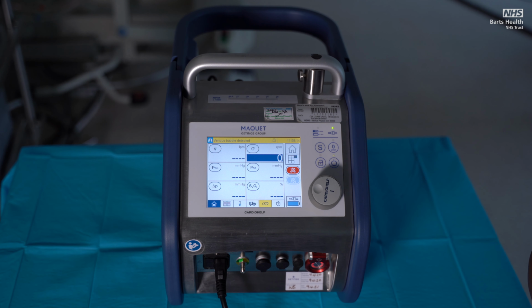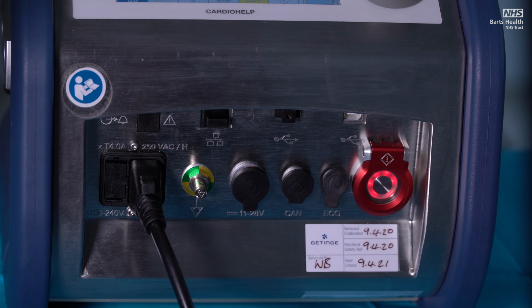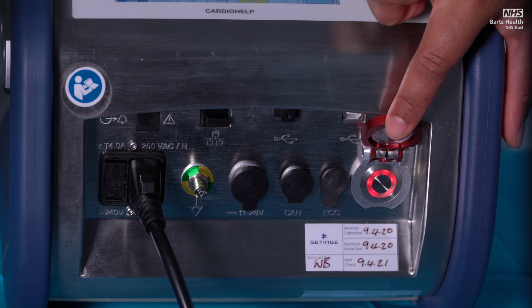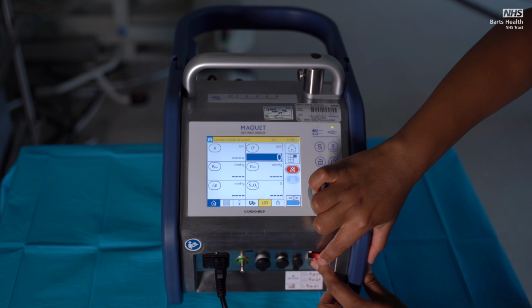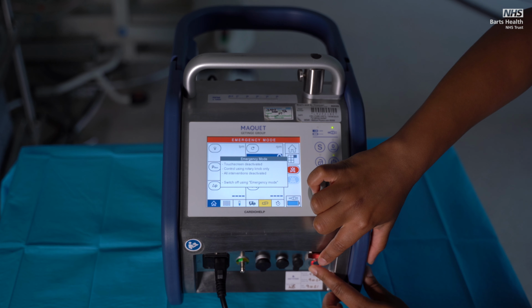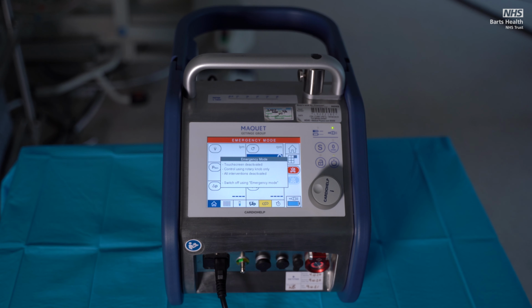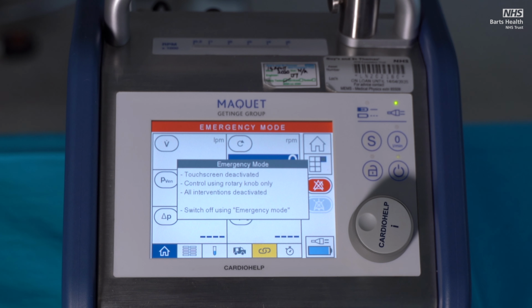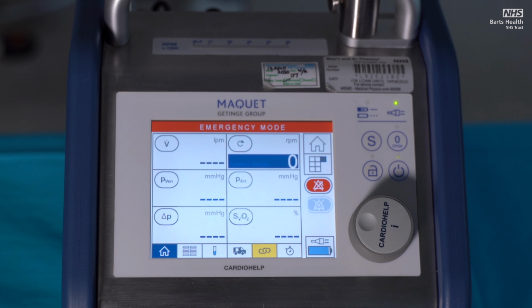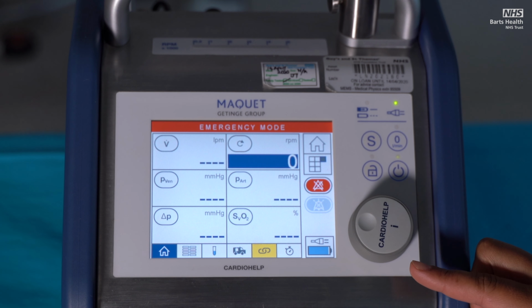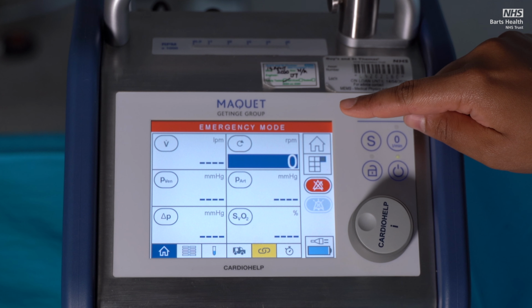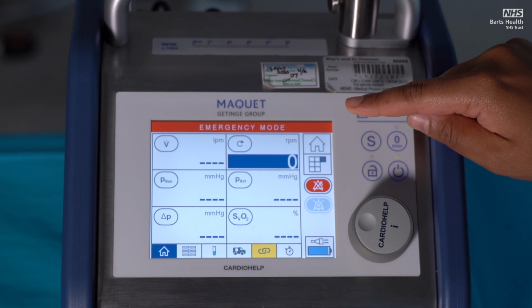In the event of a touchscreen failure, you can directly control the console by activating the emergency button found here. To do so, pull up the flap, push firmly down on the button for 3 beeps, and this will activate the emergency mode. This button overrides alarms and interventions and allows the user to control the Cardiohelp using only the rotary knob and adjusting the RPM.